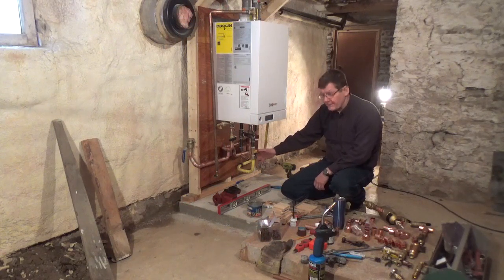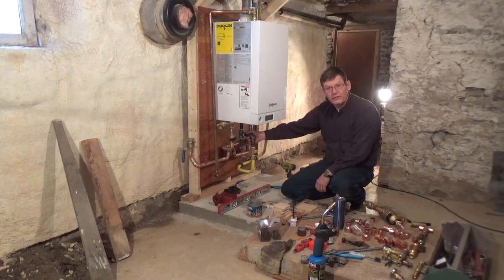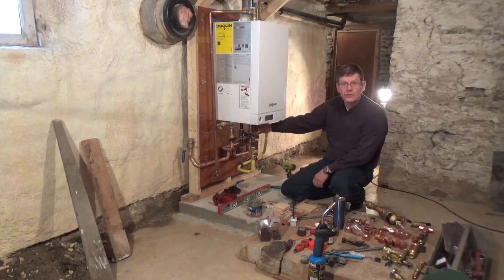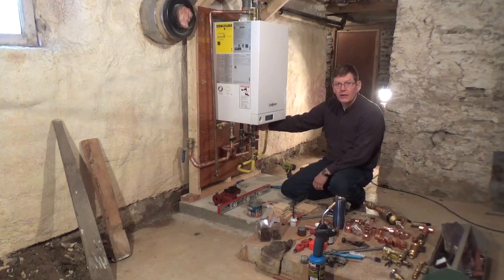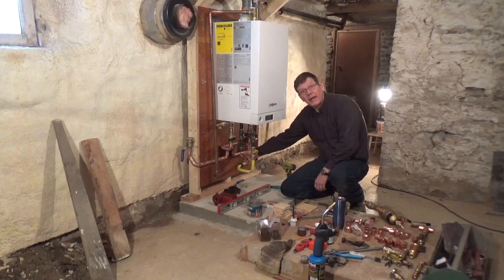Well, the manifold's all soldered, and it's all back in place in the bottom of the boiler. Now it's time to secure everything to the frame. The Viessmann installation instructions are very specific about making sure that there isn't any of the load of the piping or the weight carried on the connections to the boiler. So I'm going to fasten everything back against the wall there on some standoffs.